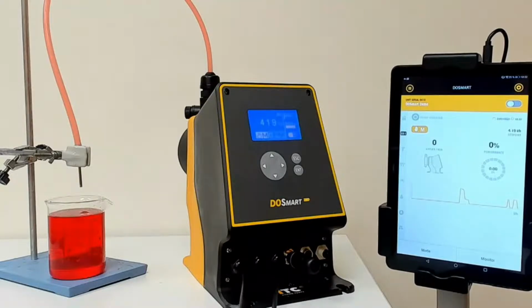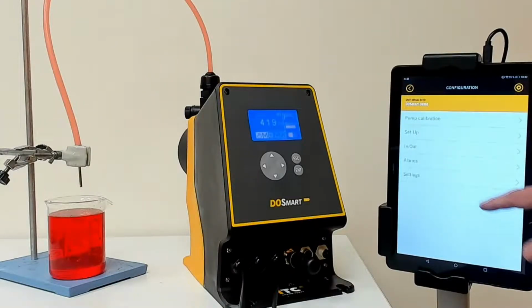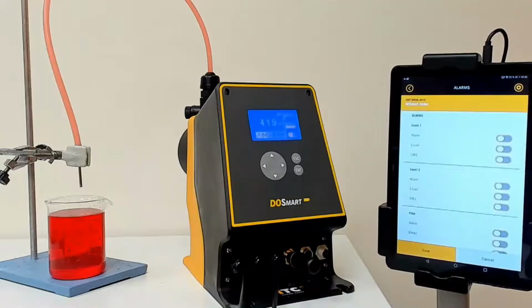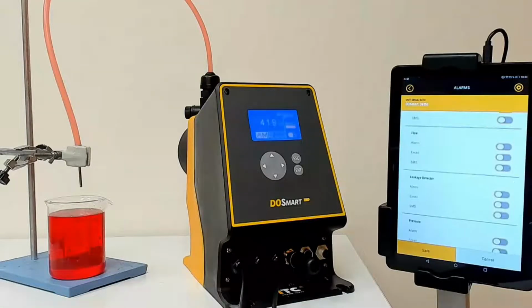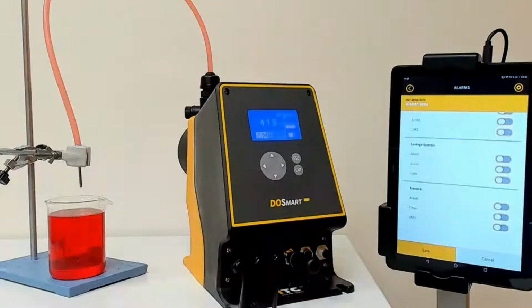At the same time, through the APP we can go through the configuration menu, where we have the different configuration options, as well as the alarms. On the alarms, we have alarms for the different safety devices that we can plug into the pump, as well as level sensors. We have two level sensors, one for warning and the other one to stop the pump. We have flow failure sensors, a diaphragm failure detector, and also pressure sensors that can be connected. All of these alarms can be configured to send an email or an SMS, or both. So you can receive this warning or alarm on your cell phone and take the required action immediately.